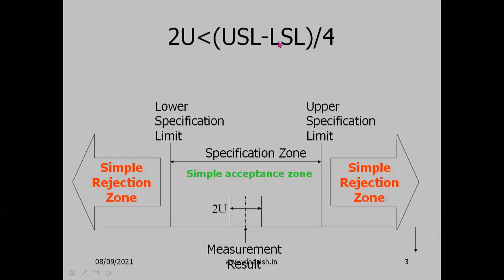The coverage interval total width should be lower than (USL minus LSL) divided by four — meaning the maximum measurement uncertainty is limited. We must ensure that 2U is less than (USL − LSL)/4. If 2U exceeds this, the measurement method is not valid and a better method must be used. If the condition is met, the instrument is acceptable.